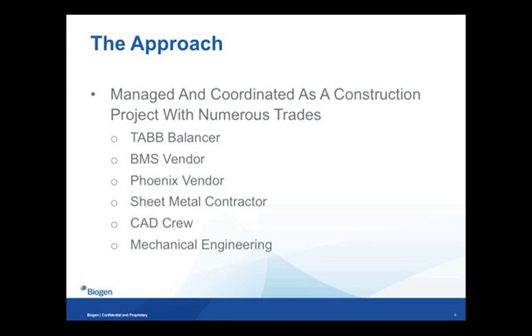Wave 2 comes after that: restore and verify. Get it back to where it needs to be. Make sure the Phoenix valves are moving, make sure the hot water reheat valves are opening and closing, that they're not jammed open, and make sure the airline isn't blowing off the pneumatic valve. Kind of the operational stuff.